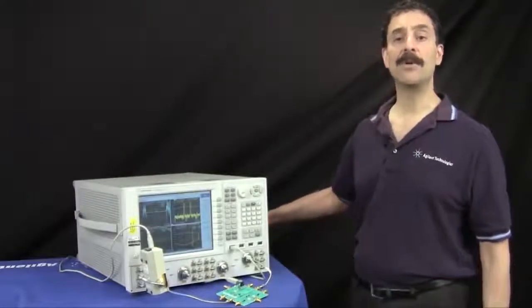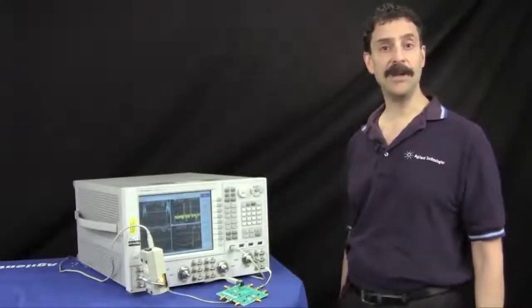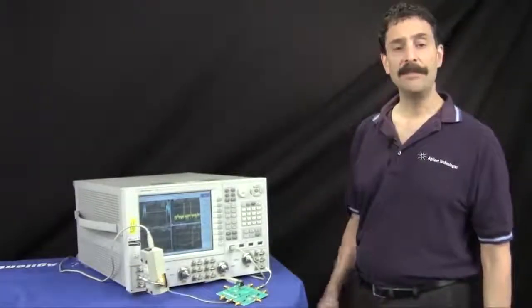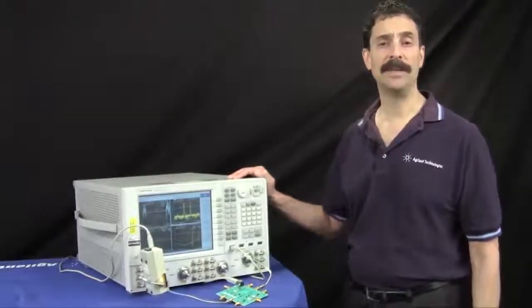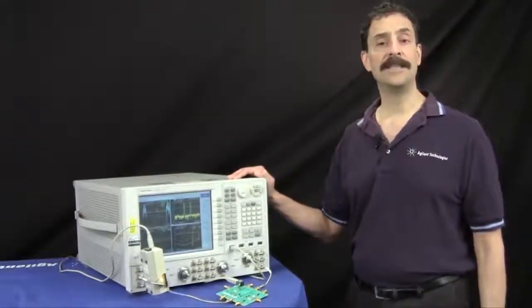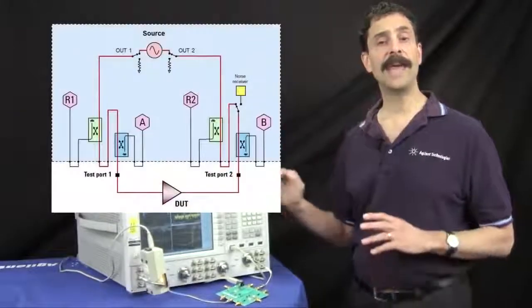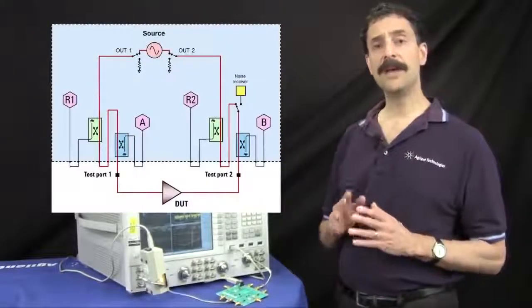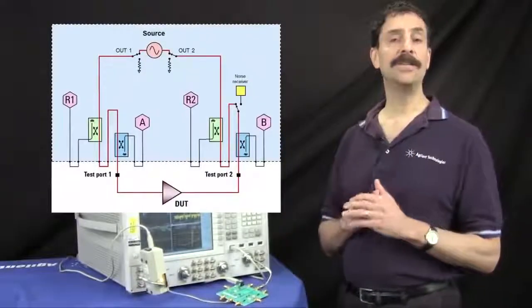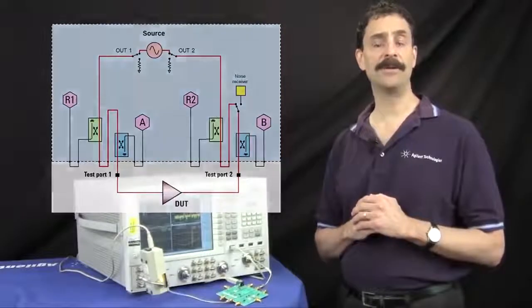Let's examine in more detail how the PNA-X measures noise figure. The PNA-X uses a cold source method, where noise figure of the DUT is calculated from two separate measurements. The first measurement is the available gain of the DUT, and this is done with great precision using vector error-corrected S-parameter measurements.